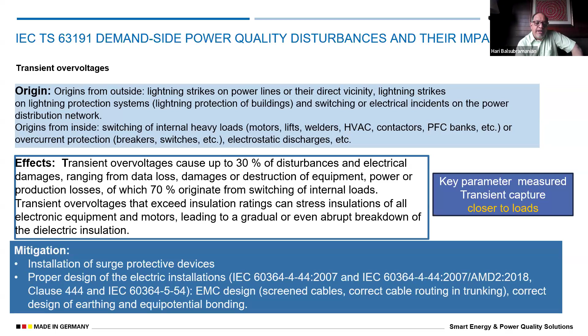The transient overvoltage causes up to 30% of the disturbances as per the standard 63191. It says 30% of disturbances happen because of transient overvoltage, and 70% of them originate from the switching of internal loads. This is a very important thing we need to understand, because in the industries they will complain: I switched on this particular load, and my system on the other side of the factory got a cable failure or an insulation failure, or some kind of tripping happened. This can potentially be due to a voltage transient. This can be mitigated by using surge protective devices, or by redesigning the system according to the proper standards. Equipotential bonding and the design of earthing also become important in this case.